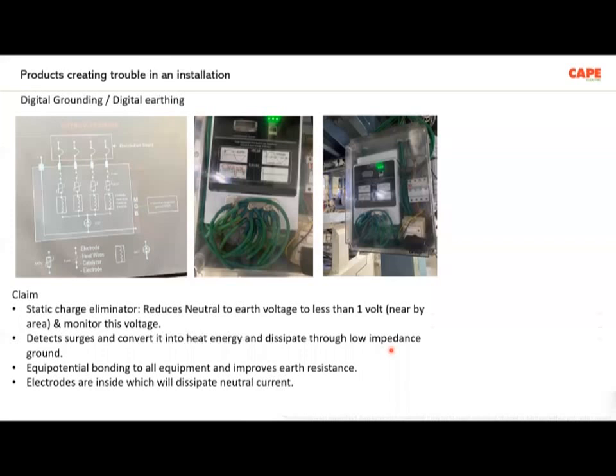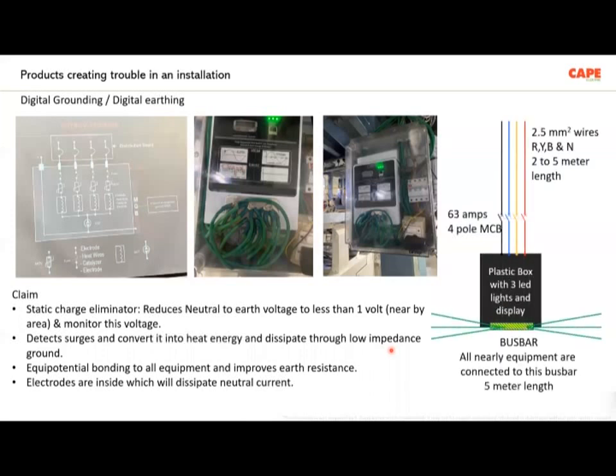But actually what they do is they short the phase and neutral inside this particular device, violating not only the regulation, it is a violation of all the safety regulations and all the safety standards. I would recommend, if you use this kind of device, please remove it immediately. These devices can create harm anytime. It can create shock hazard in your building, it can create fire hazard in your building, it can create failure of electronics in the parallel circuits.